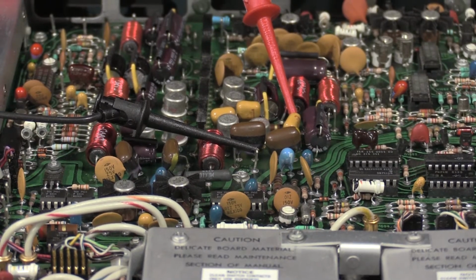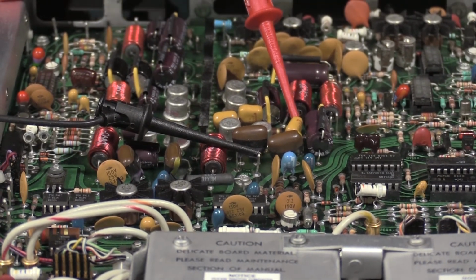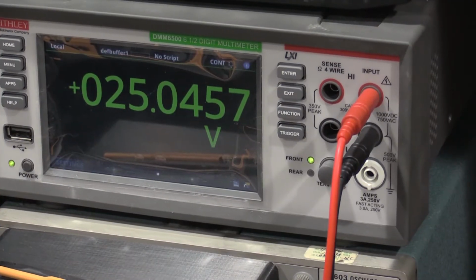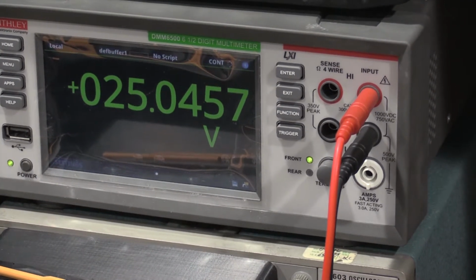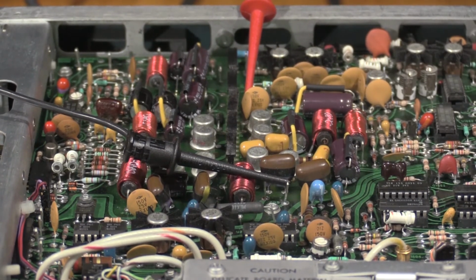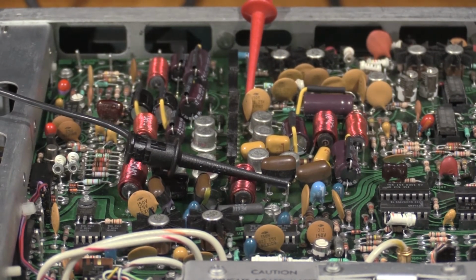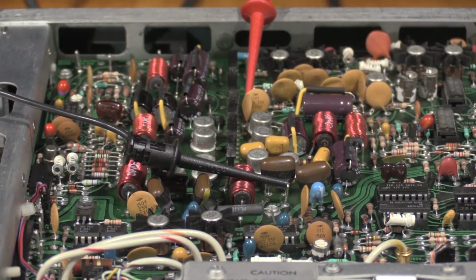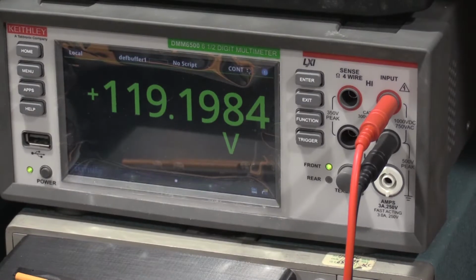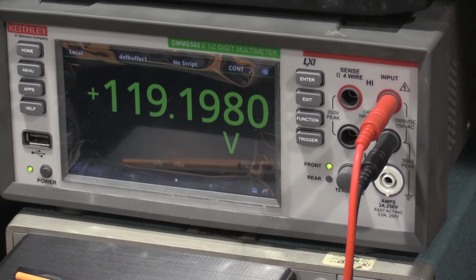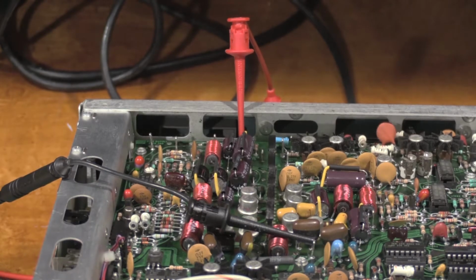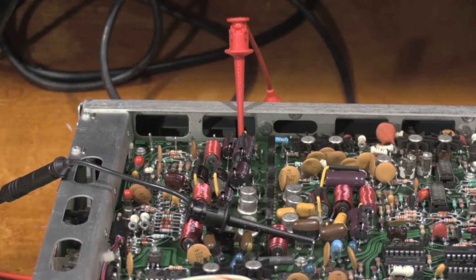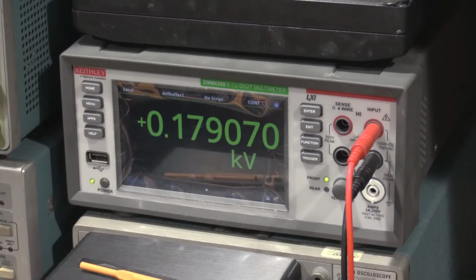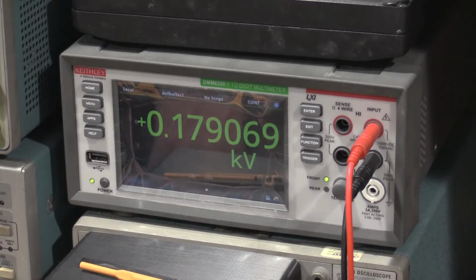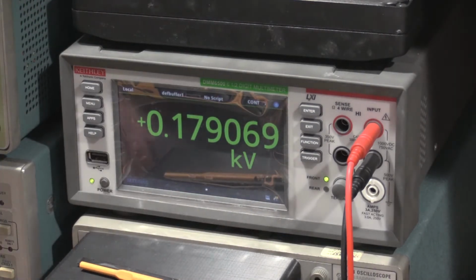Here's the setup for plus 25. Plus 25 is fine. Test point for plus 120 volts, and I'm allowed plus minus 2.4. Perfect. And here's the setup for the 180 volt test point. And tolerance on this is plus minus 3.6. So couldn't ask for better.